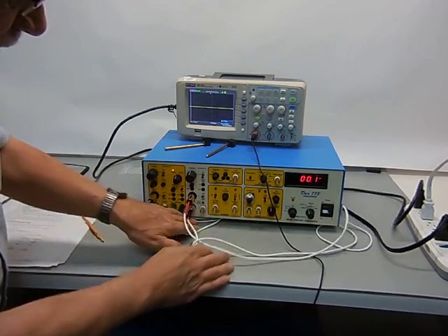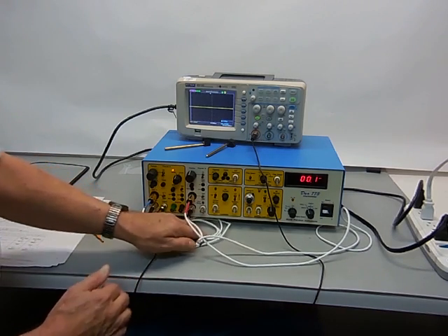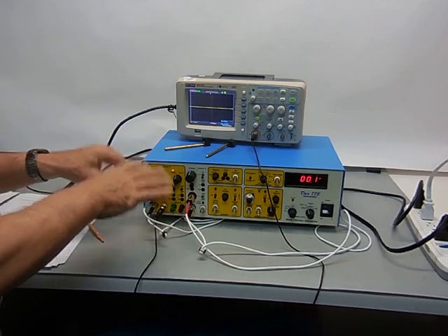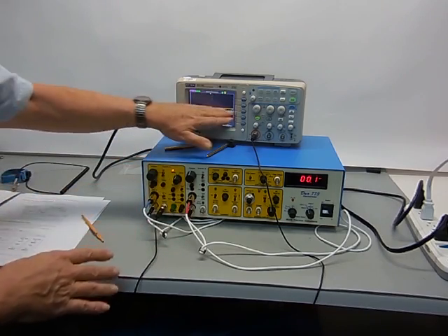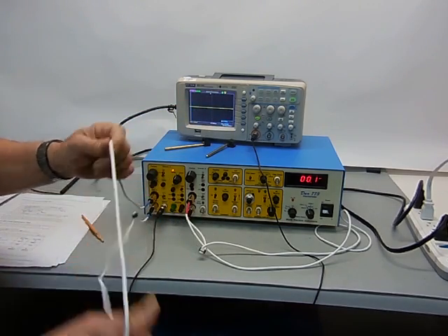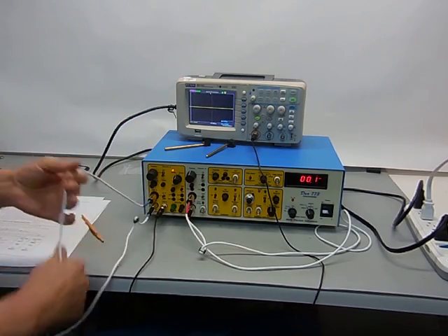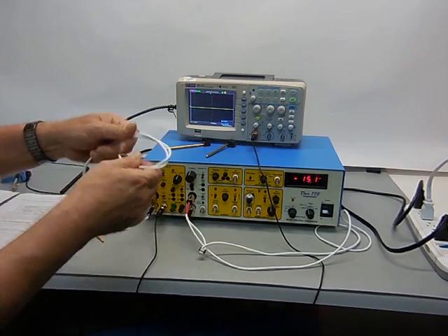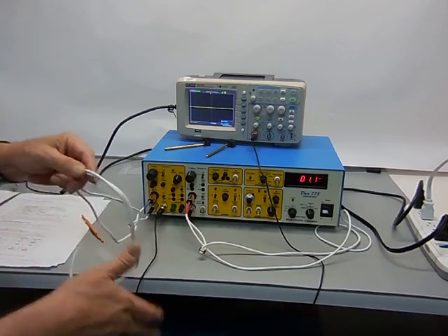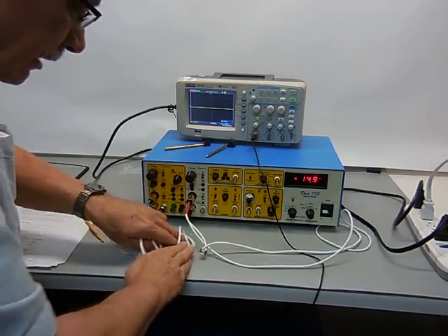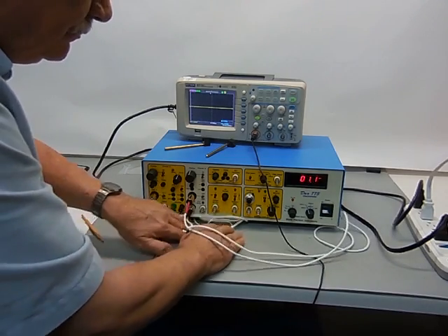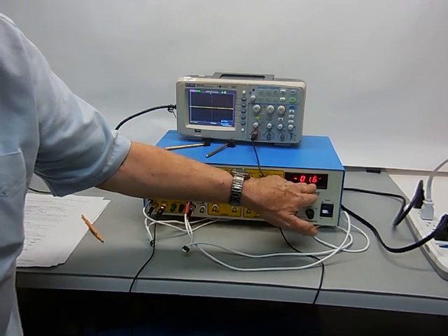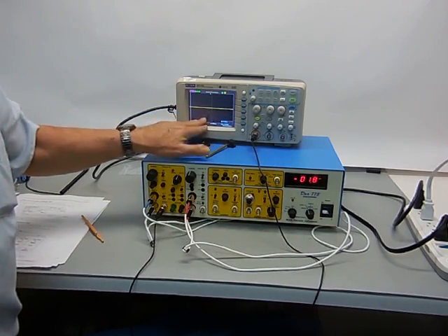I've coiled up the cable and stuffed it under the box. Channel A, under these test conditions with this very high impedance resistor, tends to oscillate. That's one of the reasons we're looking at it on the scope. If I bring this out, sometimes you can have this channel break into oscillation. I need to be in operate mode for that to occur. You can see that just by moving the cable around, there's minor changes. When you're setting this up, coil up the cable and push it under the box. The box acts as a shield and can stop oscillations. You might see a stable voltage in the meter but it could be oscillating. The only way to see that is with an oscilloscope.